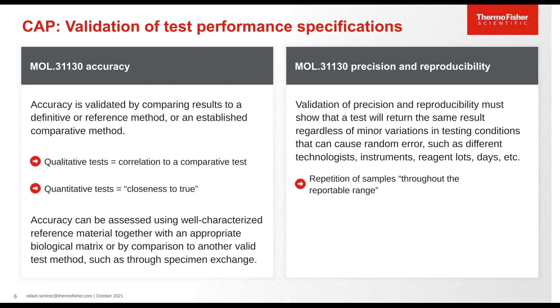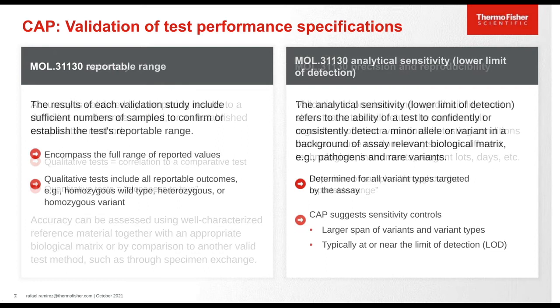Precision and reproducibility must show that the test will return the same result regardless of minor variations in testing conditions that cause random error, such as different technologists, instruments, reagents, and even days. It's important to have enough repetition of samples throughout the reportable range to establish this.